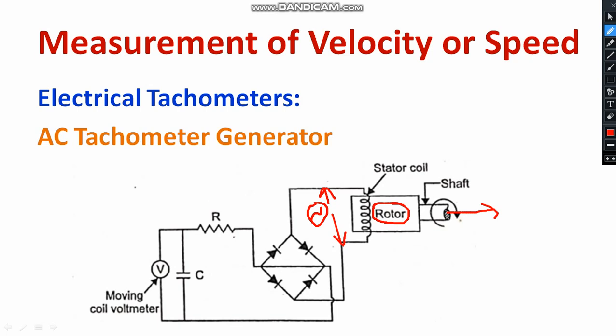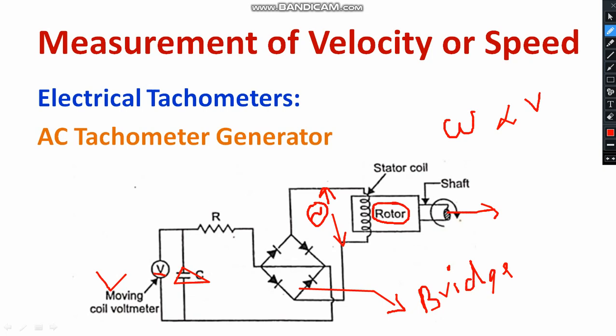The AC voltage is rectified by using a bridge rectifier. However, the output of the bridge rectifier has a certain amount of ripple content. To minimize the ripple, there is a capacitor filter. The DC output is then obtained across a moving coil voltmeter. The speed is directly proportional to the voltage generated across the filtered capacitor. This way, we avoid the usage of commutator and brushes, and smooth operation is guaranteed with the AC tachometer generator.